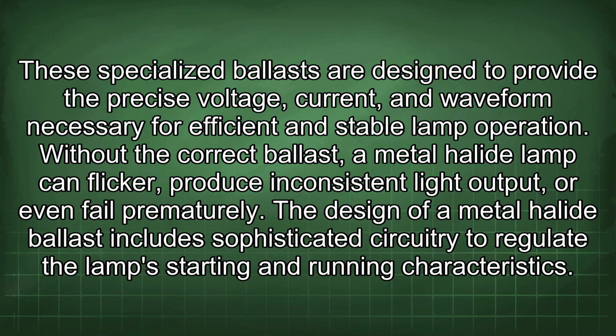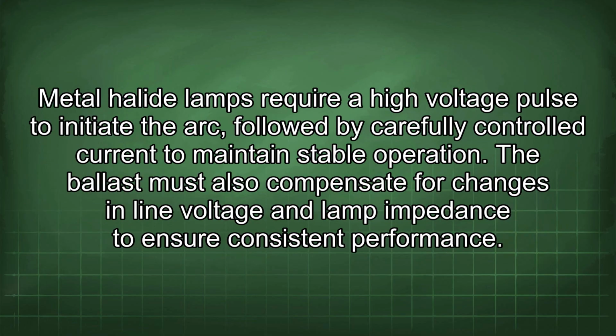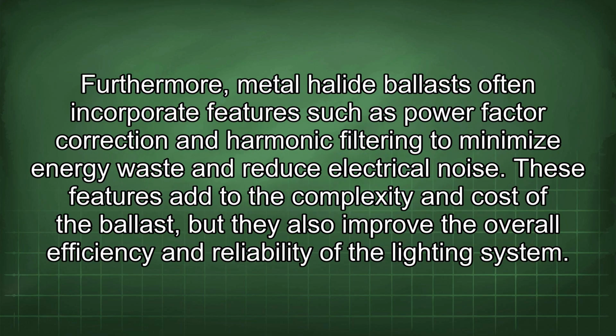The design of a metal halide ballast includes sophisticated circuitry to regulate the lamp's starting and running characteristics. Metal halide lamps require a high voltage pulse to initiate the arc, followed by carefully controlled current to maintain stable operation. The ballast must also compensate for changes in line voltage and lamp impedance to ensure consistent performance. Furthermore, metal halide ballasts often incorporate features such as power factor correction and harmonic filtering to minimize energy waste and reduce electrical noise. These features add to the complexity and cost of the ballast, but they also improve the overall efficiency and reliability of the lighting system.